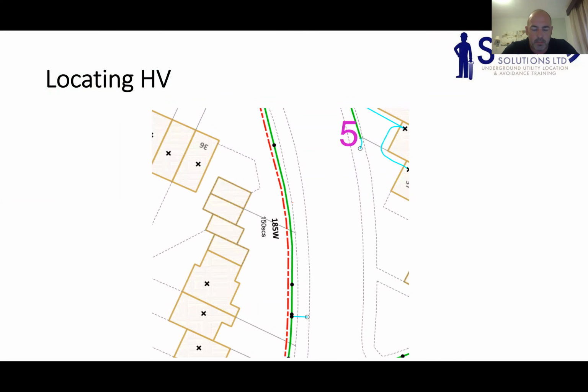So here again, UKPN. In this area here, we've got an LV, which is the green, and an HV, which is the red. The LV is easy. We can hook up to a column, we can hook up to a building. We've traced the LV. We can't find the HV though. We know it exists. The drawings are telling us it's there, but we can't find it. And so what we've tried is putting the Jenny in a few positions here, and every time we do, we only locate the LV. And as I said, it could be because we have this shallow and deep situation. So, no matter where the Jenny goes, we get this.